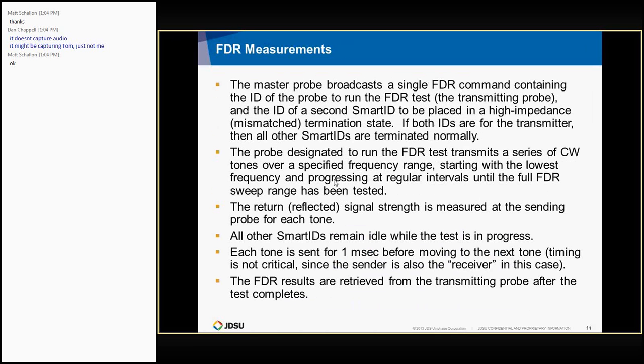FDR measurements, this is where you're actually looking for reflected power back from the sender, which is why he only needs 1 millisecond per interval, because there's nobody else out there measuring. He's the only one measuring the reflected power back to himself. So the master probe broadcasts a single FDR command containing the ID of the probe to run the test, which is the transmitter, and optionally the ID of a second smart ID to be placed in a high impedance or mismatched state. Any other smart IDs automatically attach themselves in a normal termination so that they don't generate an extra reflection. So if you want an FDR with a high impedance on one designated remote ID, you include his ID. If you want everybody listening normally, you just put in the same ID as the transmitter for the second ID.